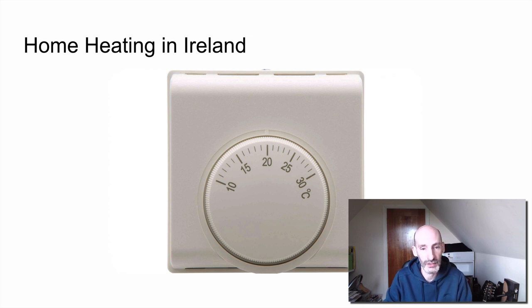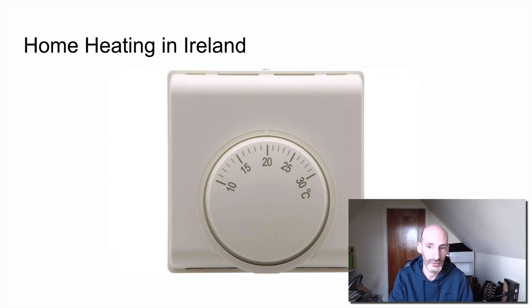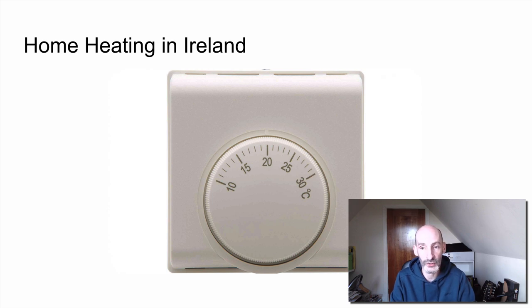Some houses, not all of them, have thermostats in addition to the controllers. With this you can set up an override: if the temperature reaches your desired temperature — for example, 20 degrees Celsius, which is about 70-71 Fahrenheit — then the heating stops running even if the programming has it running for longer. This is how you save a little heating and don't get a house that's too hot. Typically if you have two zones like downstairs and upstairs, you get one of these on each level to control your temperature.